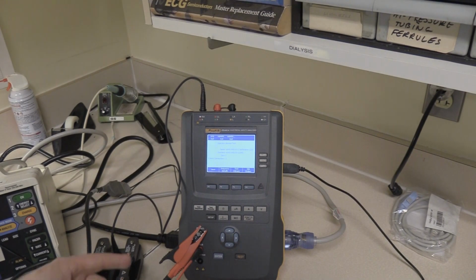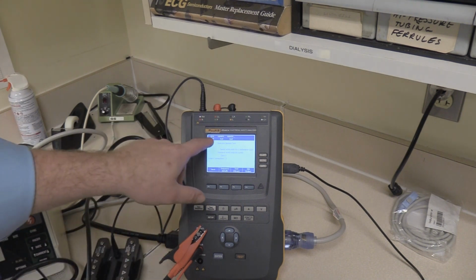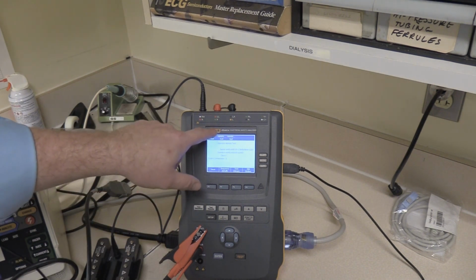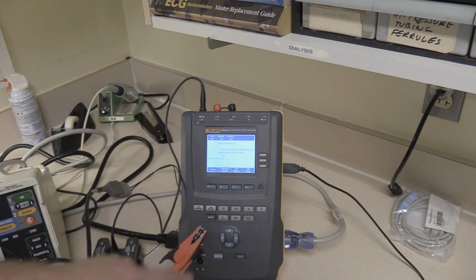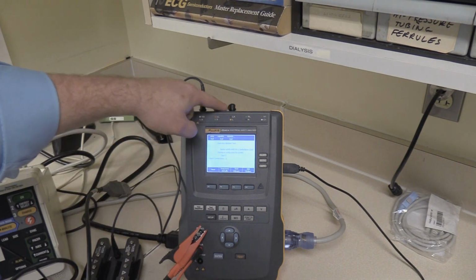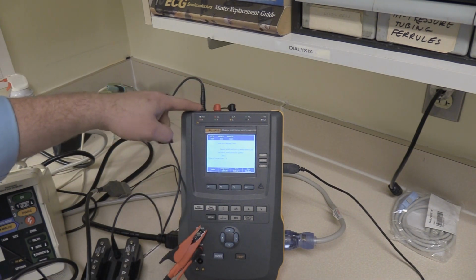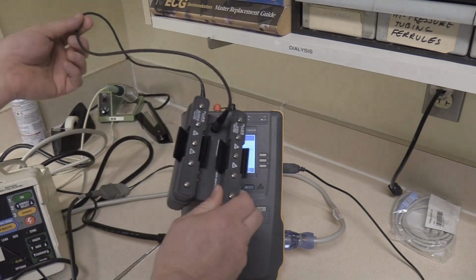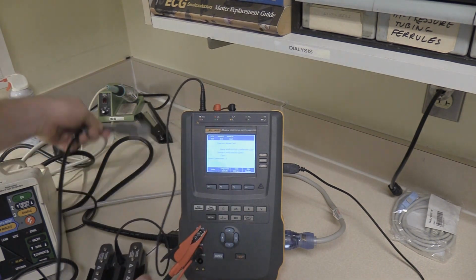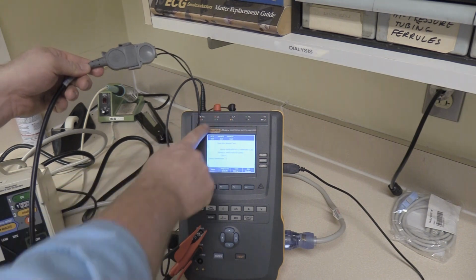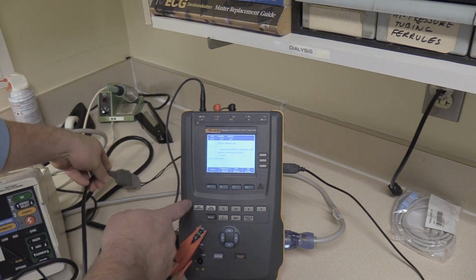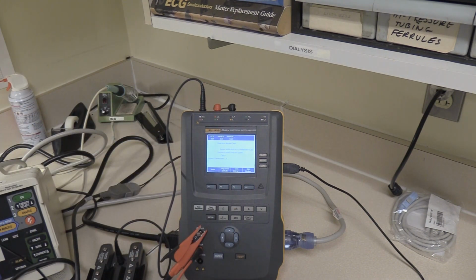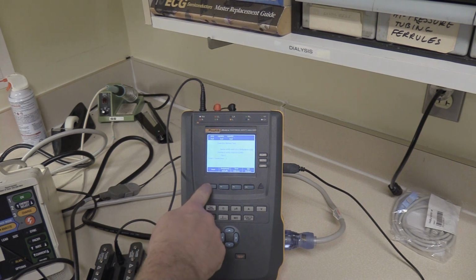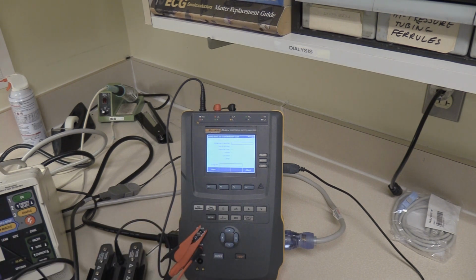All right, now we're going to review our test, and you can see at the top line here where it says ECG isolation, hands-free isolation. That's going to correspond to the connectors on the top of the ESA614. And those go down to here, the ECG to the 1 to 10 adapter, and the hands-free to the hands-free adapter. So that's a nice way to view where your connections are supposed to be. You can also review the name of the test we're about to perform. Push F1 for next to start the test.